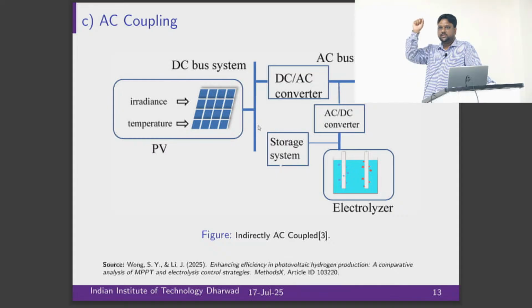So the MPPT point, as I told in the top point, right? Suddenly if my MPPT point drops, but my capacity is MPPT while I run at lower power, I will have some power reserve capacity, right? At that power reserve capacity also you should be able to operate. So when frequency drops, that power you can give to the grid. And of course, as the professor was telling, all of this is tariff based. So the utility operator will give you some kind of benefits for providing these services.